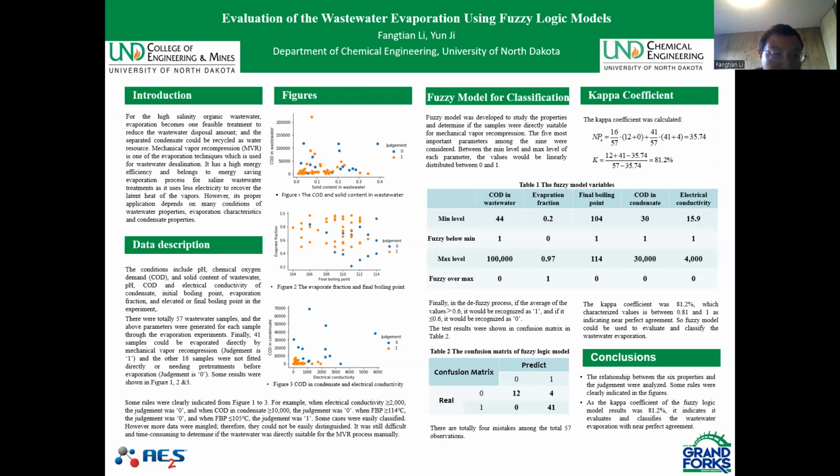However, its application depends on many conditions. In this study, at least 9 conditions: 3 from wastewater, pH, chemical oxygen demand (COD), and solid content; 3 from condensate, pH, COD, and electrical conductivity; and 3 from the evaporation process, initial boiling point, evaporation fraction, and elevated or final boiling point.